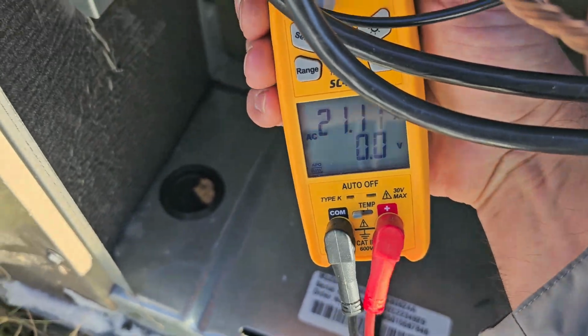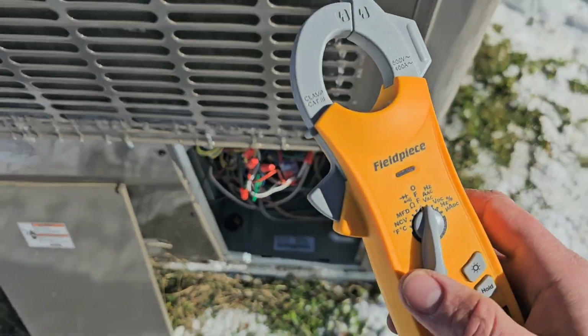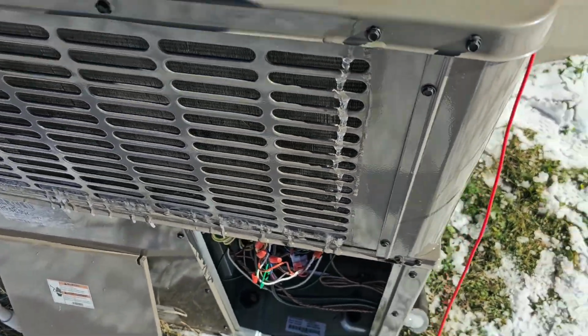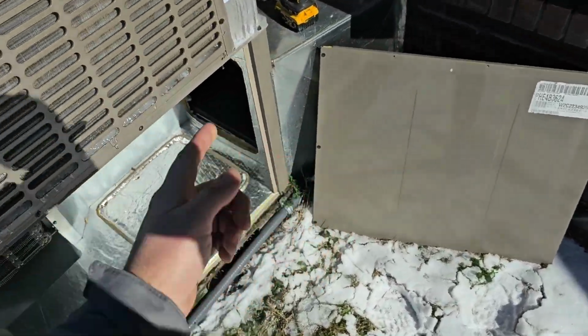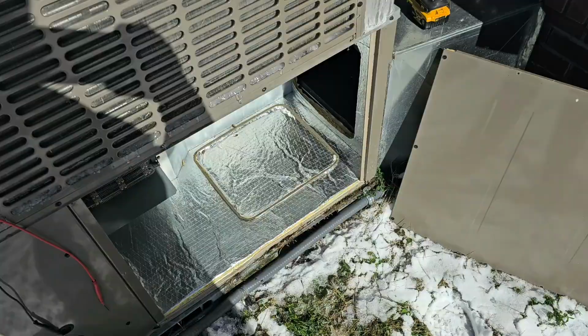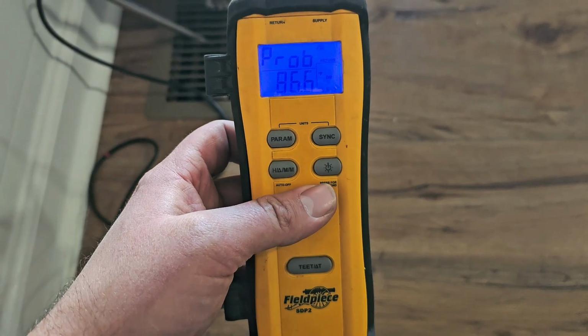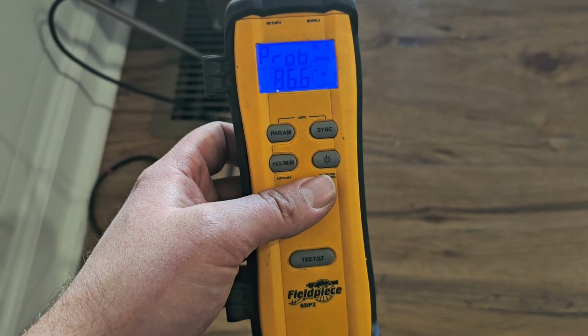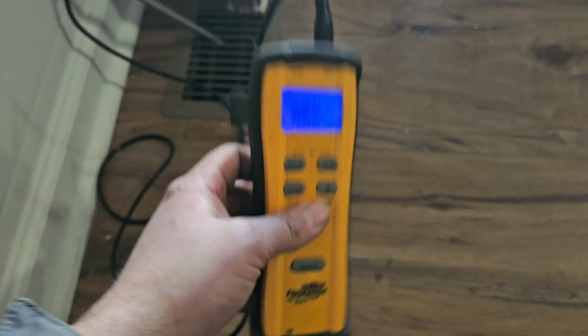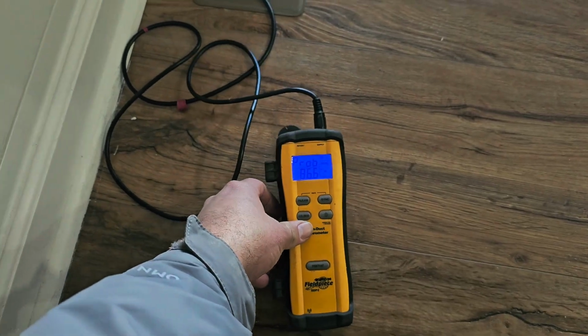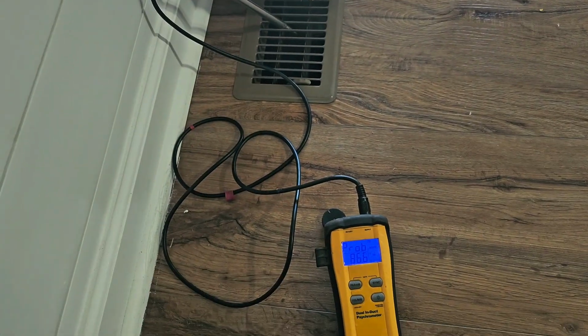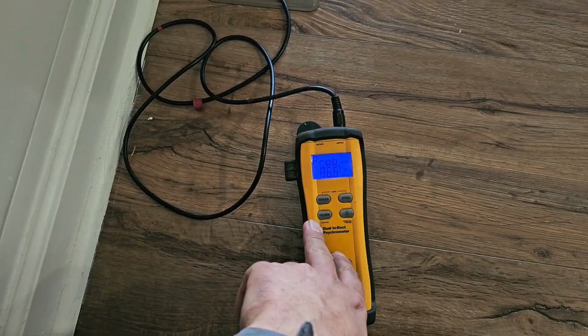20 amps, well, 21. So 10 kW, 40 amps, it's working. I'm gonna put the panel back on and we'll measure the supply temperature inside the house. Supply temperature is now 86.6. So we've got a 20 degree split between the return and supply temp, and it's working as it should.